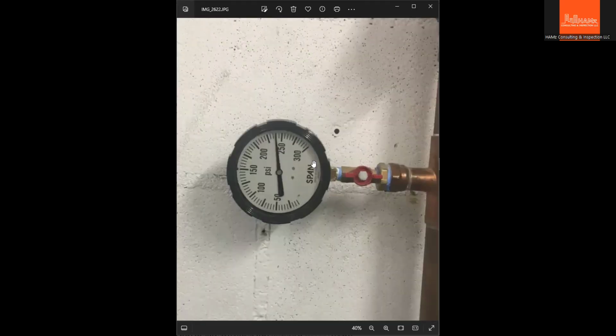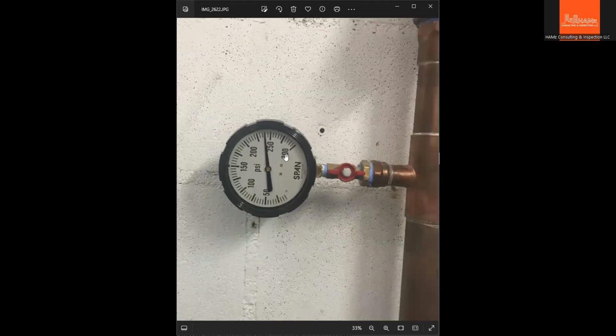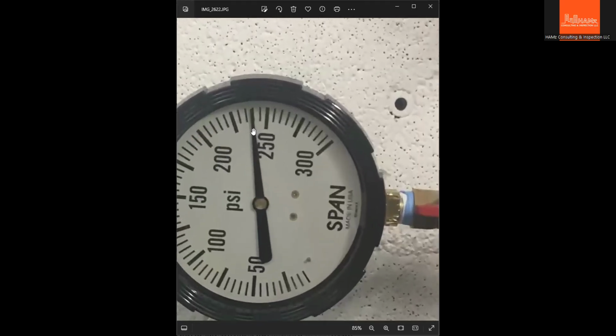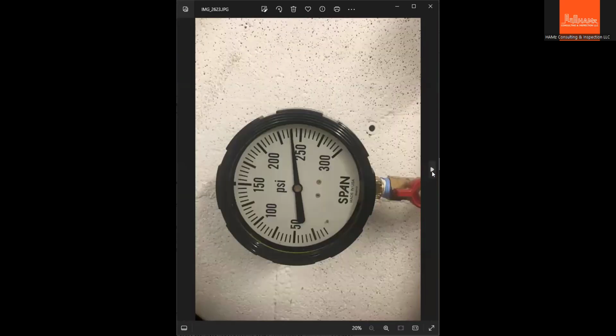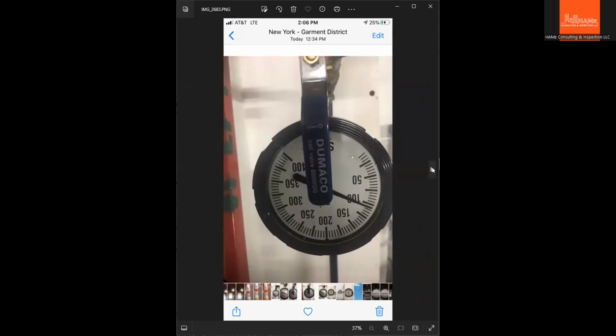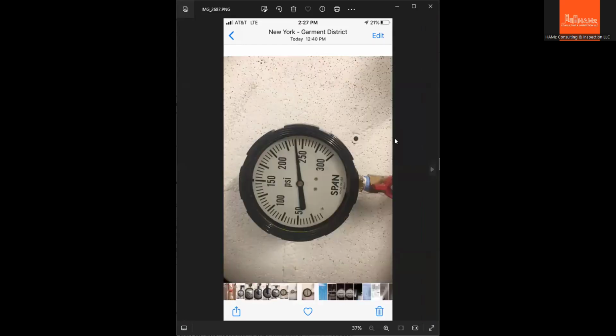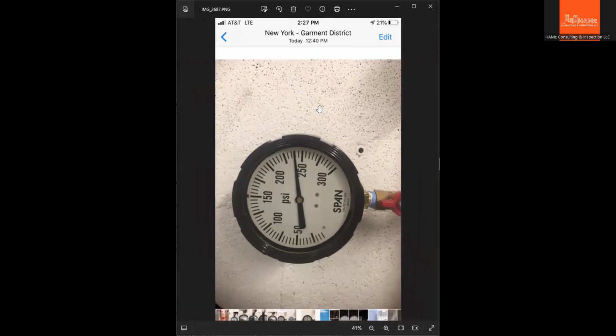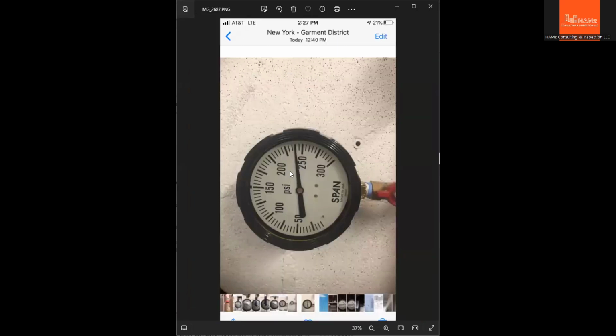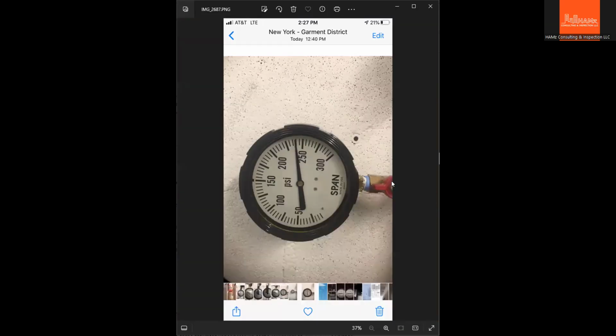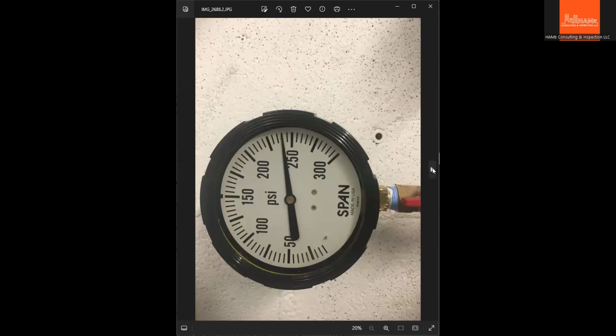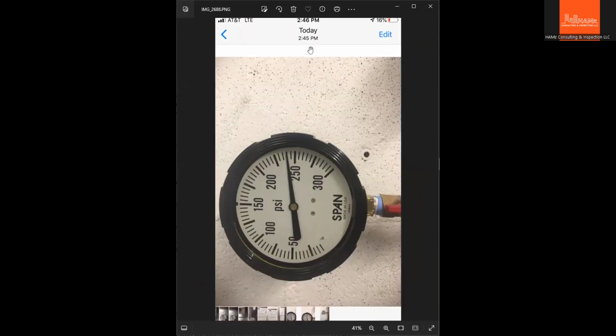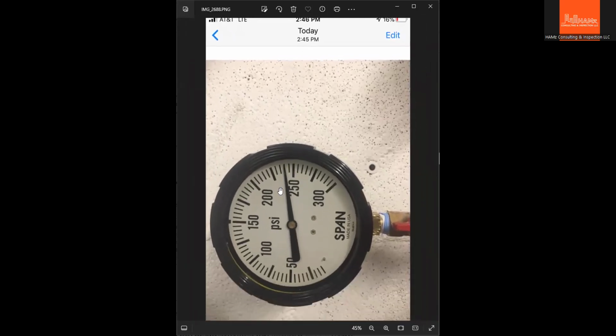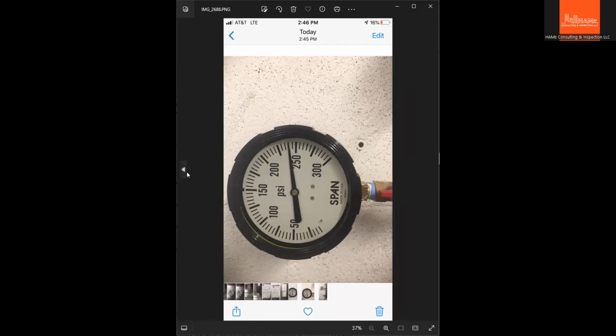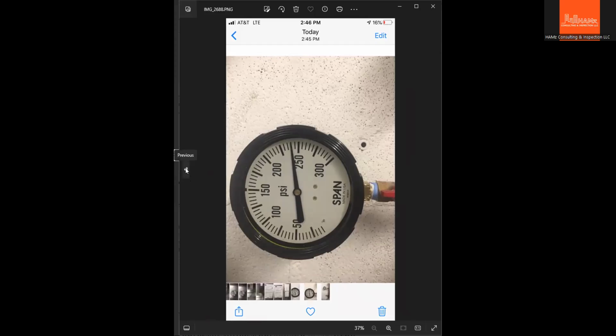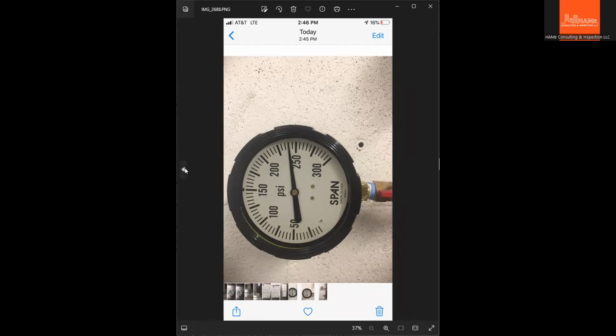And this is the time that we pumped up the chill water piping. So right now we are at exactly 240 psi. A closer look. Oh, this is the same pipe. So this was taken at 12:40 p.m. and then at the 2:27 screenshot, the pressure was still at 240 psi. So after 2 hours, now it's 2:45, still 240 psi. So it means the chill water piping system is leak free, no pressure drop, and no visible leaks.